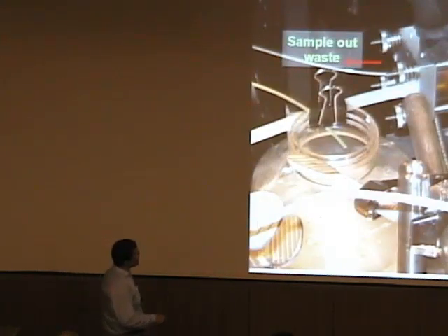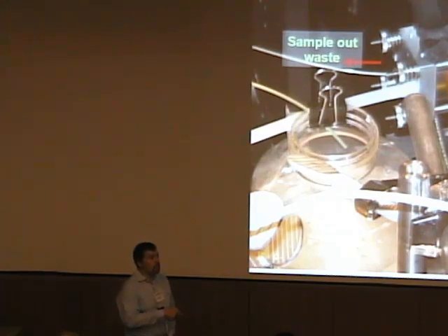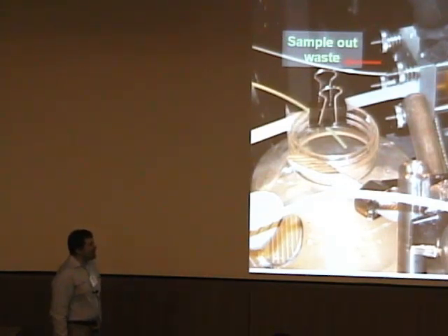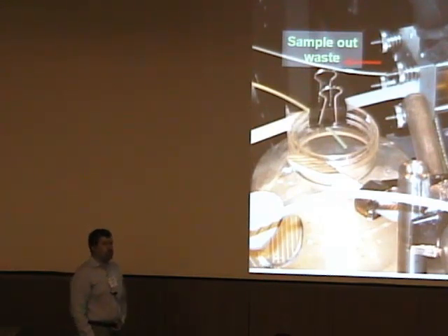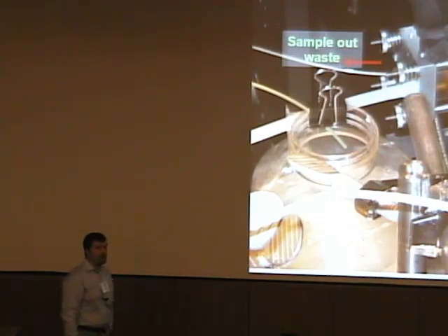This is a close look at our system. This is our mixer. The beam is brought from the bottom. This is the collection lens. We bring the sample in with a counter flow of cold nitrogen, pre-cooling the sample before the mixing takes place. This is temperature-controlled gas, and the sample is exhausted here. So typically, we like to work on a few seconds time frame delays at those temperatures. Again, I can tell you a lot more with practical examples in the Raman practical room.